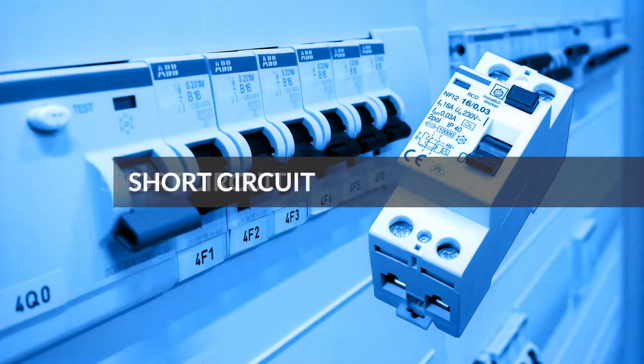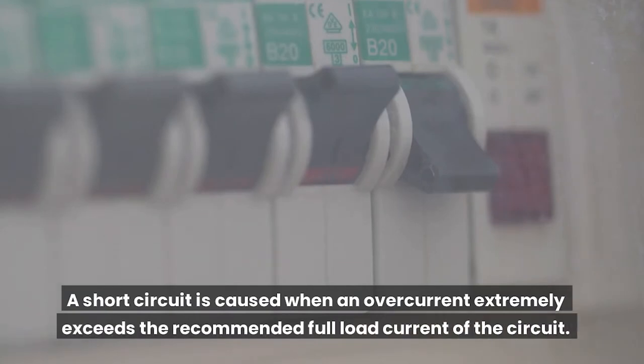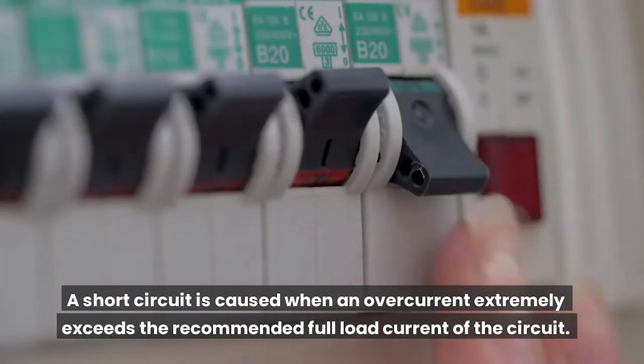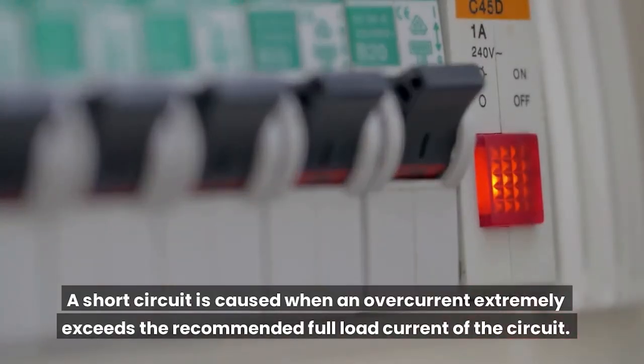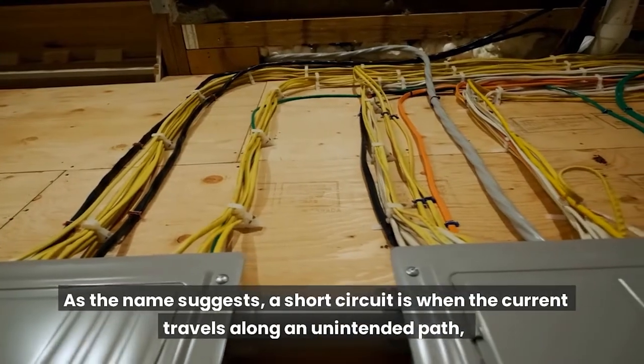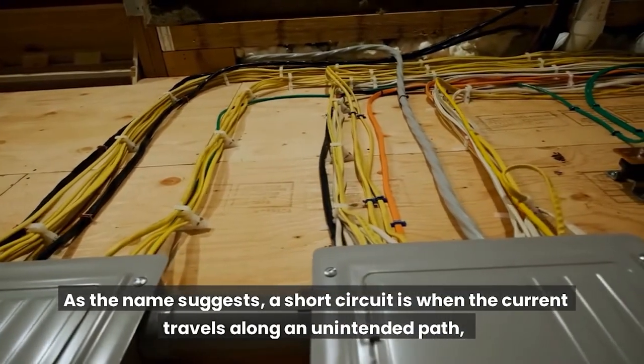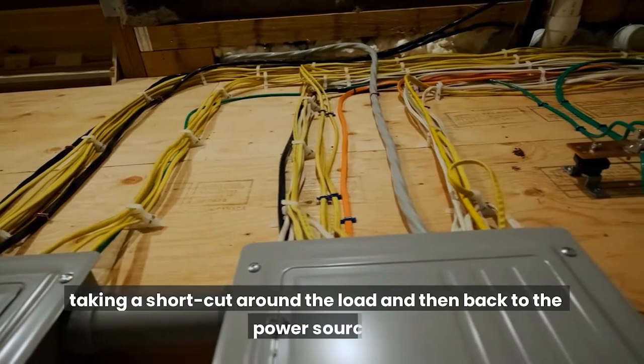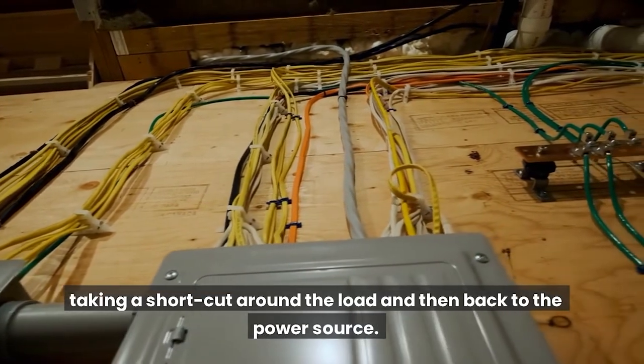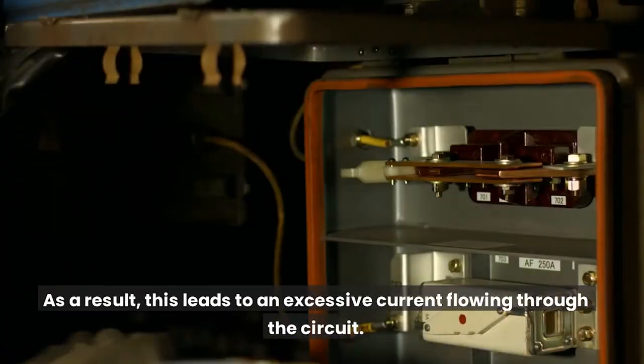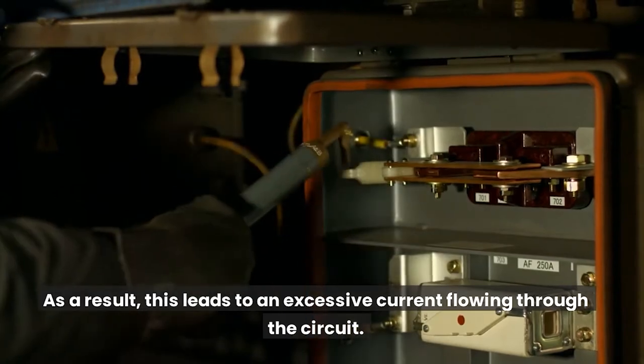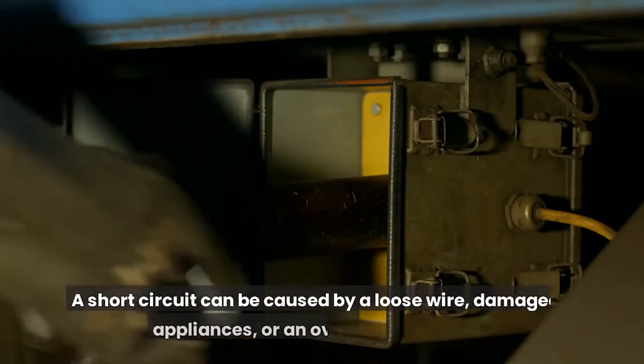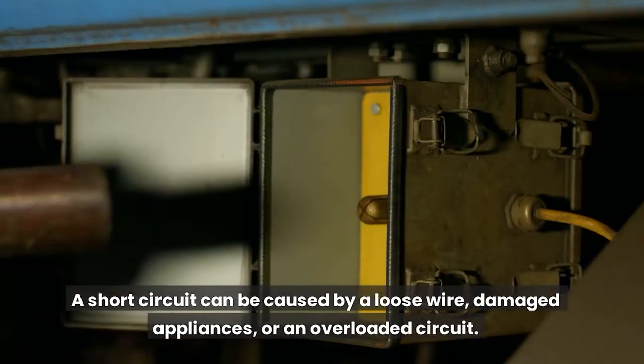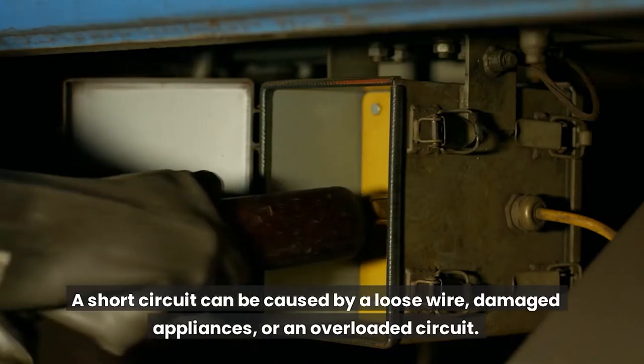Short circuit. A short circuit is caused when an overcurrent extremely exceeds the recommended full load current of the circuit. As the name suggests, a short circuit is when the current travels along an unintended path, taking a shortcut around the load and then back to the power source. As a result, this leads to an excessive current flowing through the circuit. A short circuit can be caused by a loose wire, damaged appliances, or an overloaded circuit.